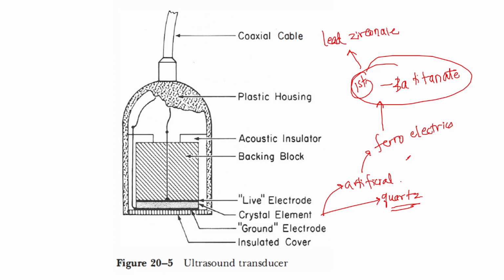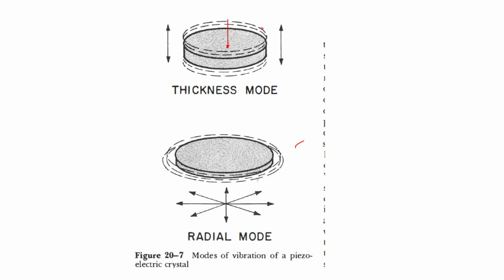Lead zirconate titanate is the most commonly used ferroelectric or piezoelectric chemical in ultrasonography. The main advantage of this piezoelectric ceramic is that it can be deformed into different shapes, based on the application which is needed. So if you see, this is the normal thickness of the piezoelectric crystal. When the acoustic impulse, the reflected sound echo, reaches this crystal, it will vibrate.